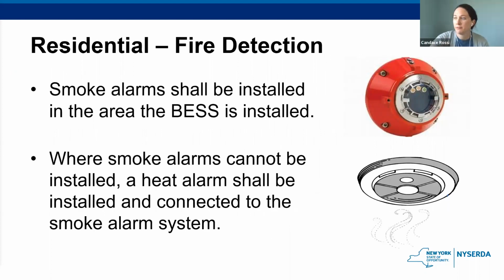Once again, we have a fire detection requirement for residential systems. Smoke alarms shall be installed in the area where the energy system is installed. And where smoke alarms cannot be installed, a heat alarm shall be installed and connected to the smoke alarm system. I think most of us probably have smoke alarms throughout our house, which would be sufficient. But for projects installed in your garage, there are not always smoke alarms installed there, and sometimes a heat alarm will be installed instead. So you just need to make sure that one of these is installed, so that if there is an issue, an alarm is sent.